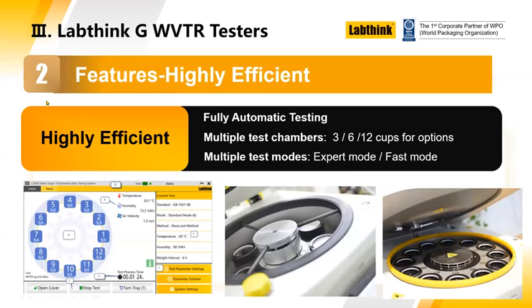It's very efficient. Multiple test cups, 3, 6 or 12 cups, are options available. This means that you can test, for example, 4 sets of triplicates in one pass, in one machine. We advise you that although you can use different materials and mix them up inside the machine, it's better to try and keep the barrier properties of the material somewhat similar.